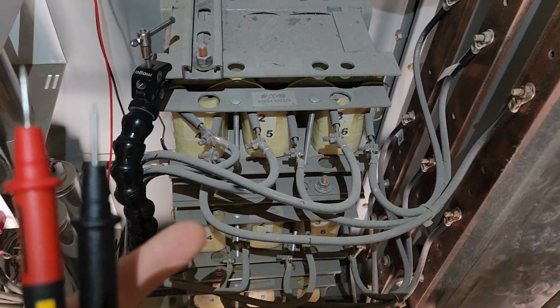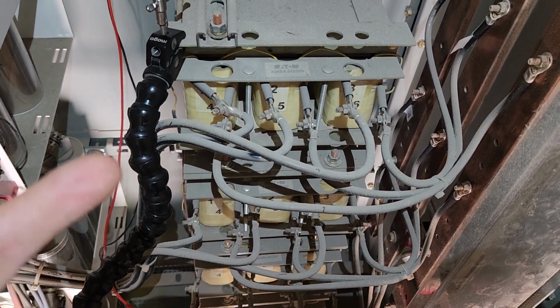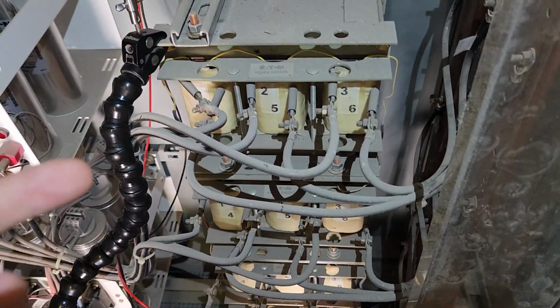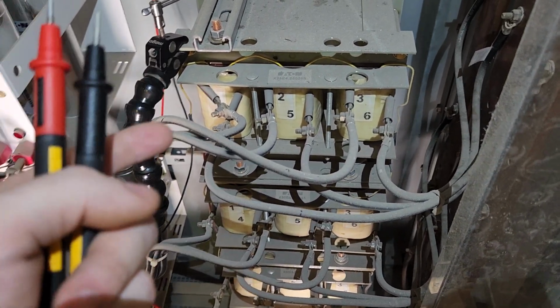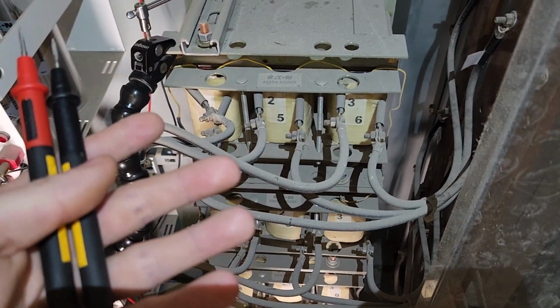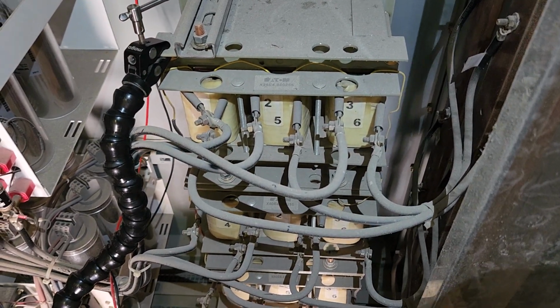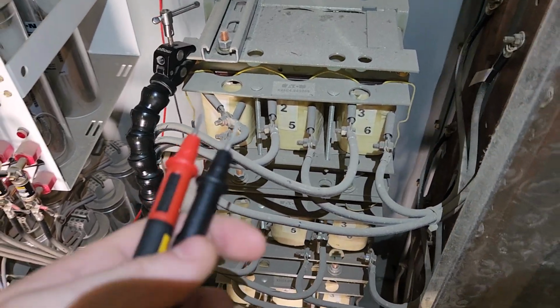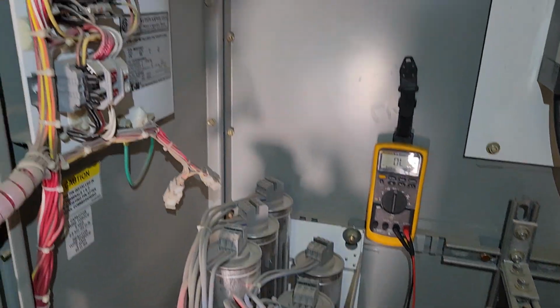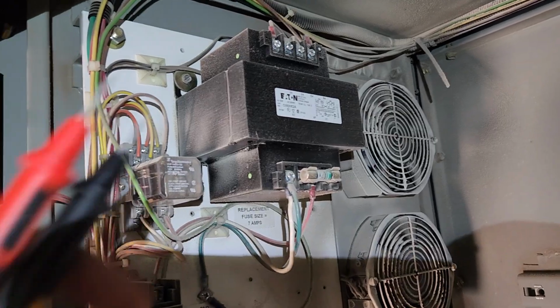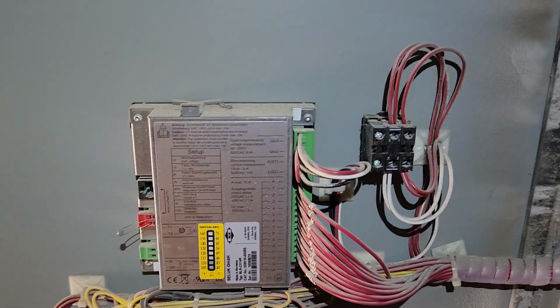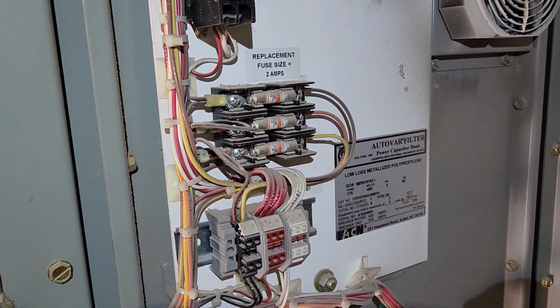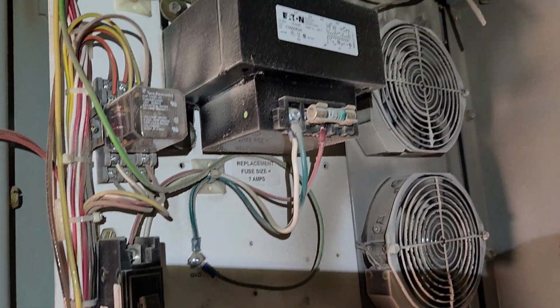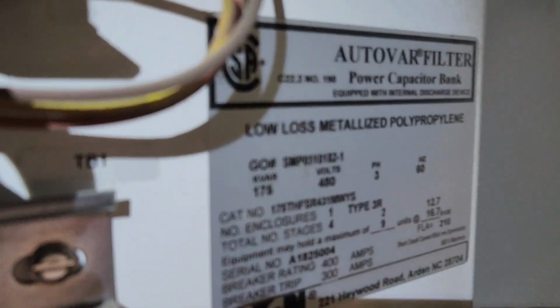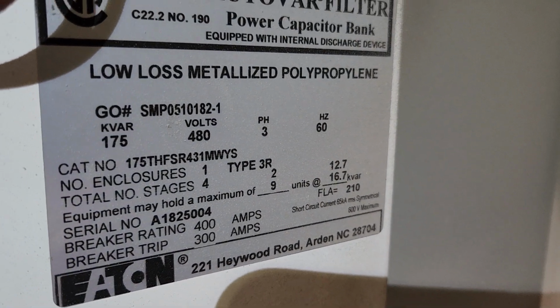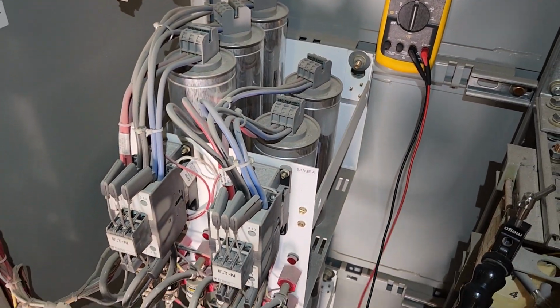The reactors, you can actually check just like you check an inductive motor winding, where you go ground to the reactor with a megohmmeter. And I think these are like 2.5 megaohms, or 2.5 million ohms, per reactor phase to ground of resistance. So you could check them too, but we're not having issues with these at the moment as far as I can tell. So anyways, thought you guys might find that kind of interesting. Up here we got a transformer for control voltage. A couple fuses coming in. Those are 2 amp fuses. We got a 7 amp fuse up here at the transformer. And you can see here 175 kVARs, 210 full load amps on these capacitors, which is fairly substantial.